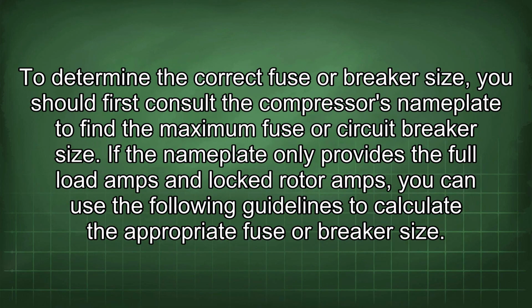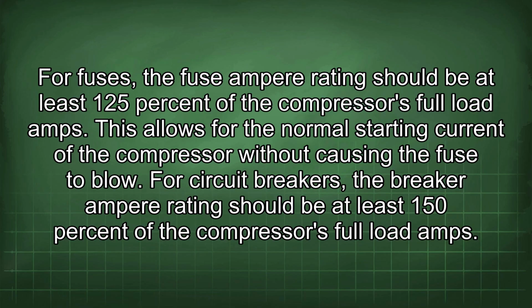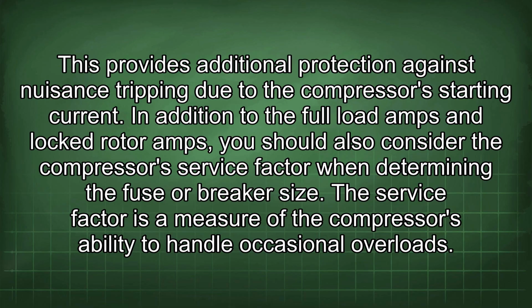To determine the correct fuse or breaker size, you should first consult the compressor's nameplate to find the maximum fuse or circuit breaker size. If the nameplate only provides the full load amps and locked rotor amps, you can use the following guidelines to calculate the appropriate fuse or breaker size. For fuses, the fuse ampere rating should be at least 125% of the compressor's full load amps. This allows for the normal starting current of the compressor without causing the fuse to blow. For circuit breakers, the breaker ampere rating should be at least 150% of the compressor's full load amps. This provides additional protection against nuisance tripping due to the compressor's starting current.